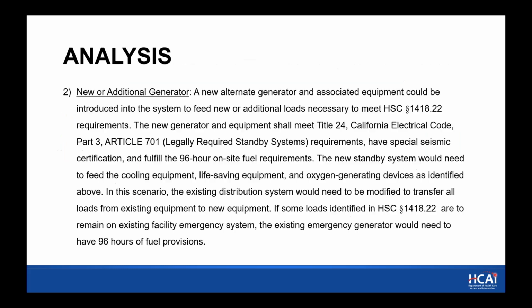The next scenario, number 2, is a new or additional generator. In this case, a new alternate generator and associated equipment could be introduced to the system to feed new or additional loads to meet the new requirements. The new generator and equipment should meet Title 24 Electric Code Article 701, legally required standby system requirements, and have special seismic certification and provision for 96 hours of on-site fuel storage. The new standby system would need to feed the cooling equipment, life-saving equipment, and oxygen generating devices as identified above. In this scenario, the existing distribution system would need to be modified to transfer all loads required by this bill to be backed up from existing equipment to new equipment.